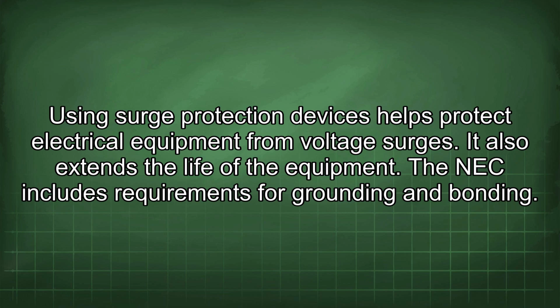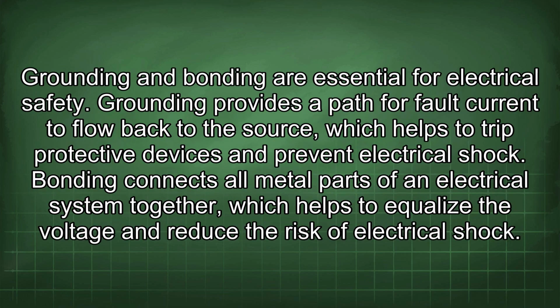The NEC includes requirements for grounding and bonding. Grounding and bonding are essential for electrical safety. Grounding provides a path for fault current to flow back to the source, which helps to trip protective devices and prevent electrical shock. Bonding connects all metal parts of an electrical system together, which helps to equalize the voltage and reduce the risk of electrical shock.